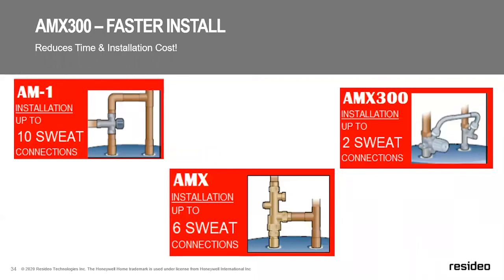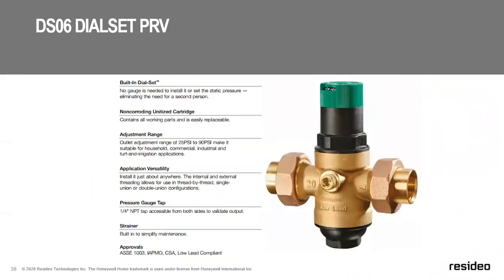Our AM1 provides more sweat connections, but it's great for an indirect hot water heater. We have that available in multiple ways. We now have ProPress, sweat, thread, PEX, you name it. We have an AMX, which is in the bottom middle there. That's really good because it's a device mixing valve that can get a lot of flow through it. So if you're working on a higher end home, maybe large capacity or it's light commercial, that mixing valve there can handle a lot higher flow ratings. And then we have the AMX300, which only requires up to 2 sweat connections to get installed. And that's shown on the top right in the mixing valve we previously discussed. Staying with the potable, let's talk about pressure reducing valves for a whole house.